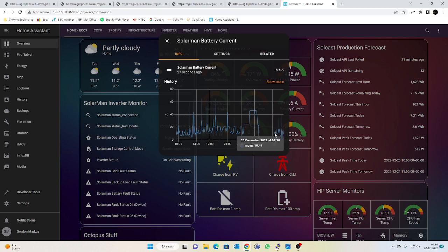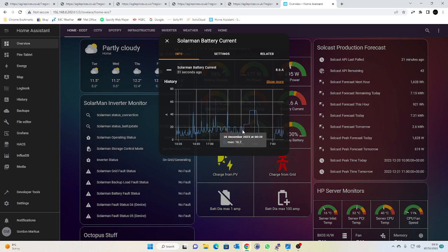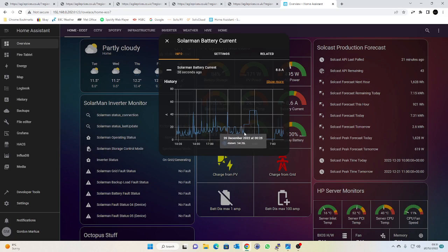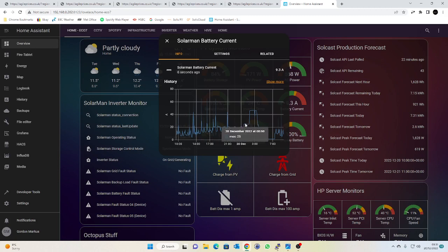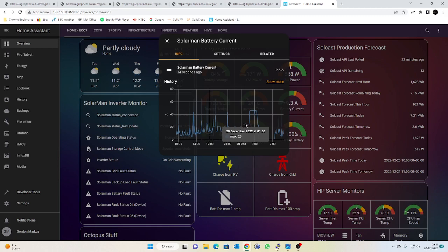And then we can see that we start to get some actual usage out of my batteries. Also we can see overnight here, here's where it's charging from grid. So the graphs aren't great there we go, 35 minutes past midnight my charge amps increases to 45 and because of where my batteries are located which is actually in a sort of cupboard outside and underneath the house they're actually pretty cold out there, and it's the middle of winter here at the moment. So the Fox batteries actually limit themselves to a 12 amp charge when it's below 15 degrees I think. So what we can see there is because I've got two of them the current is 25 amps while the batteries are cold and then it kicks up to 45 once they warm up and they've been charging for a little while.